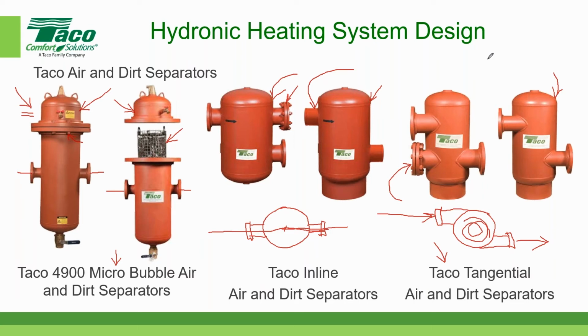Yes, on the previous discussion where we talked about expansion tanks, there is no detrimental effect to the operating characteristics of a hydronic system if the expansion tank is larger than what it needs to be. If you make the expansion tank larger, the only real penalty is the cost of the expansion tank. You'll be paying more money for a larger tank and the amount of physical space or real estate that the tank will take up. So there's no operational penalty, but there is a space and cost penalty.